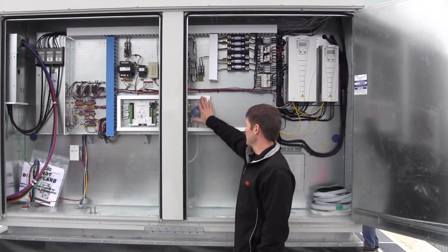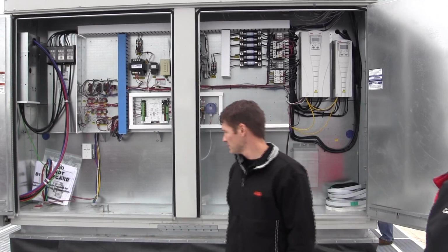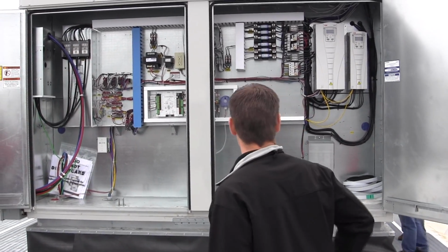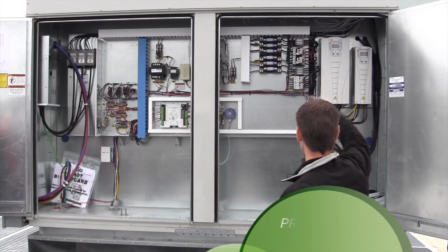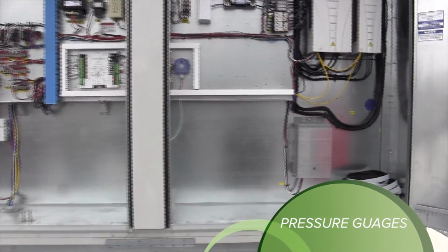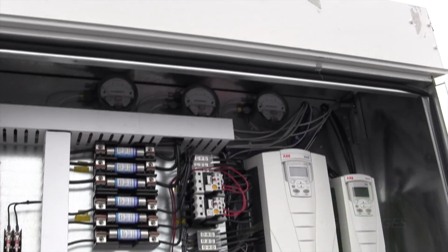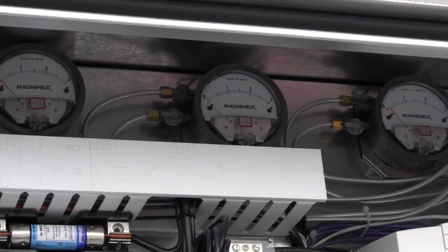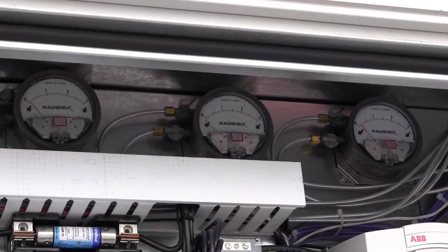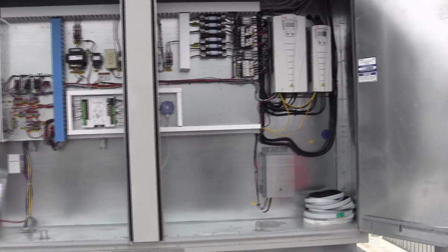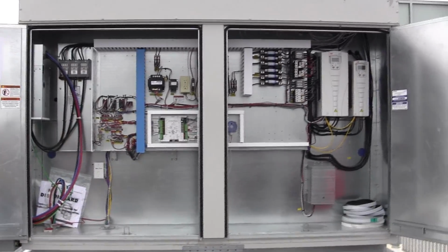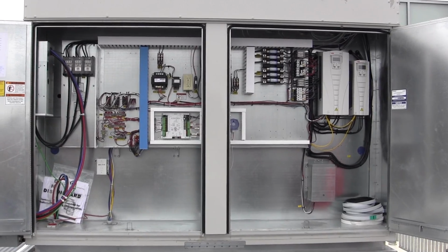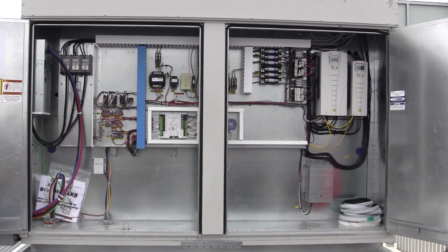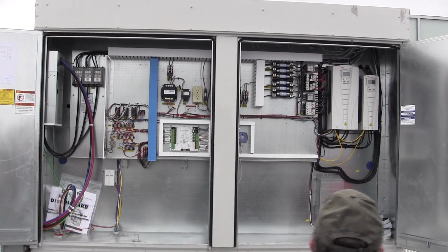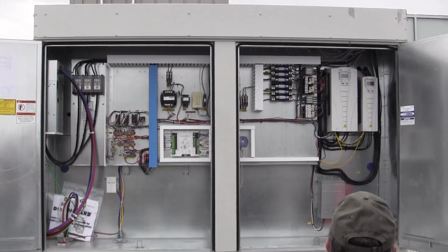And then they field installed fire alarm stuff here. So quiet, it's nice. And then up here are your Magnehelic pressure gauges for filters, and they all read 0. It must be very clean, huh? Did you put those in? Well, a lot of times you zero it when you put in a clean filter, and then when it goes over an inch above, you change it. So they probably haven't been zeroed out.